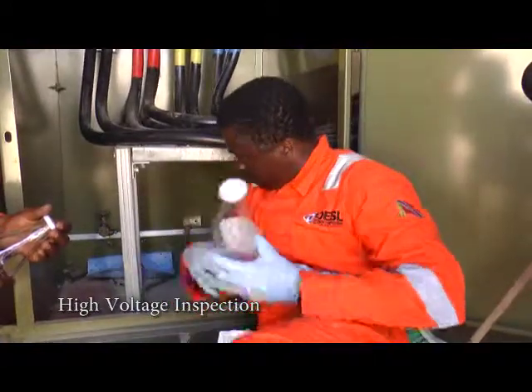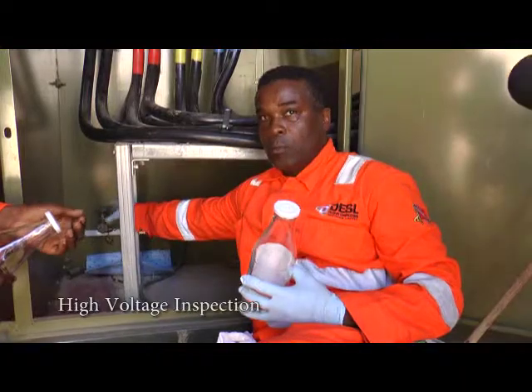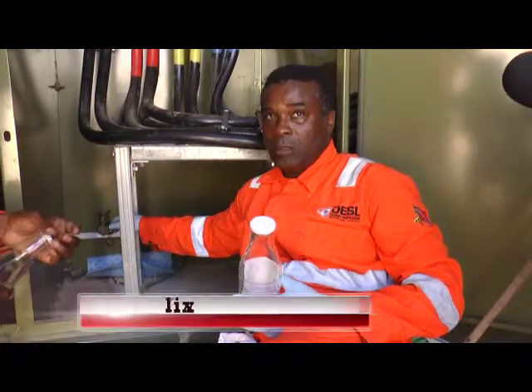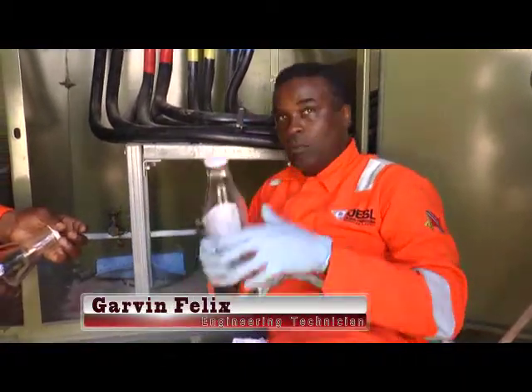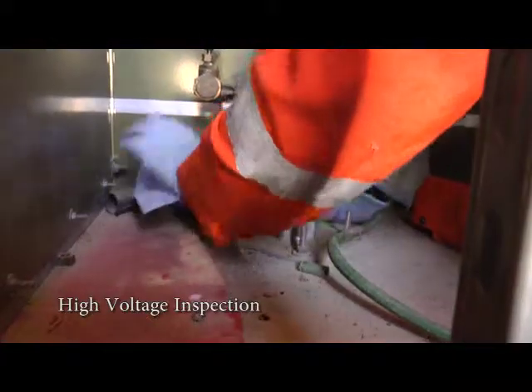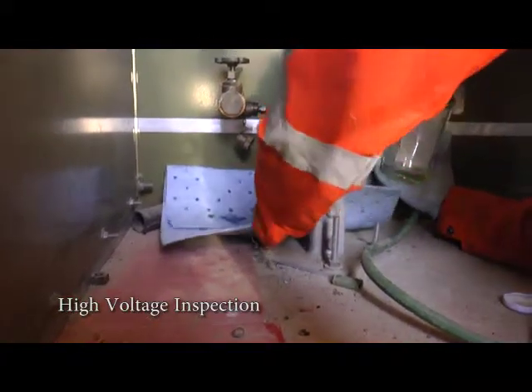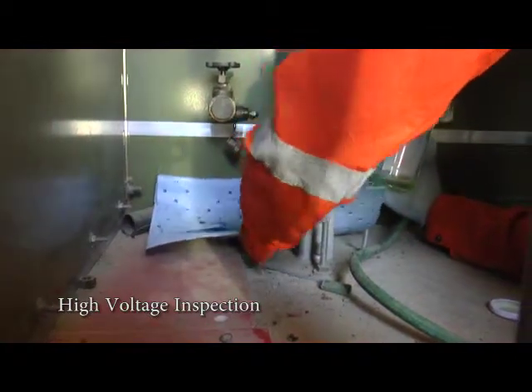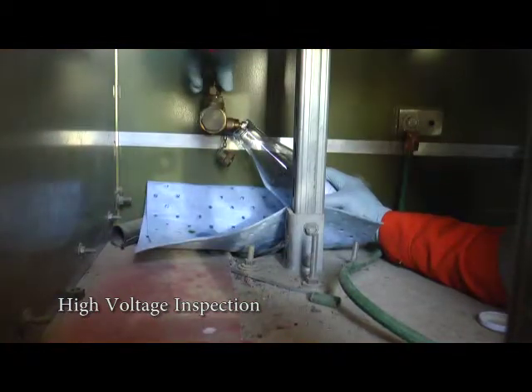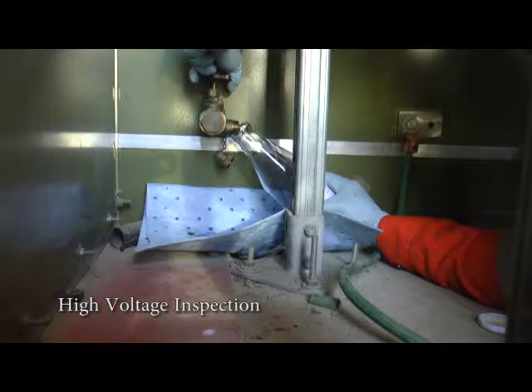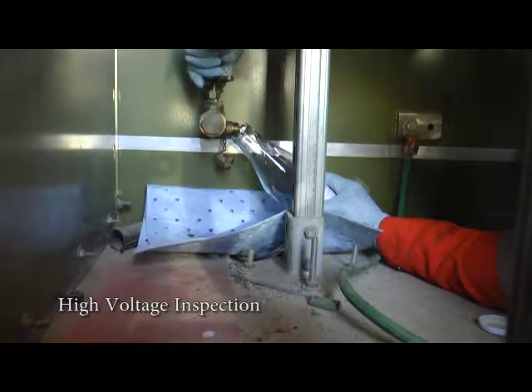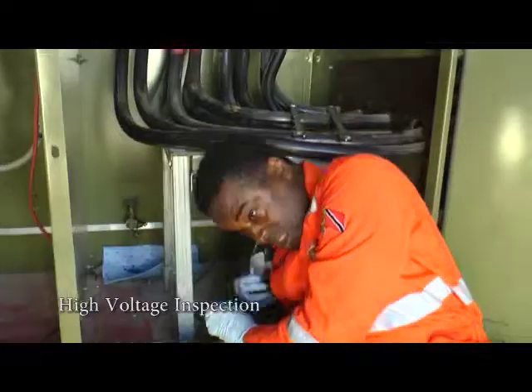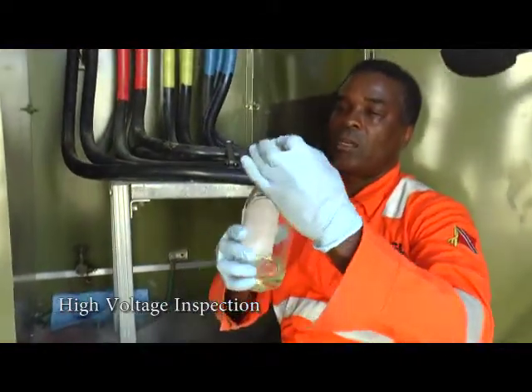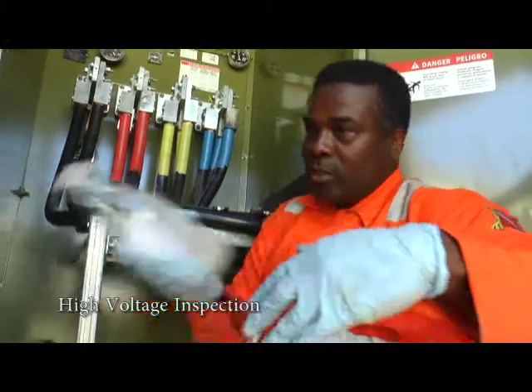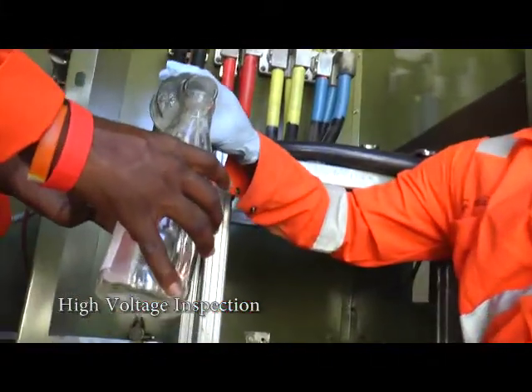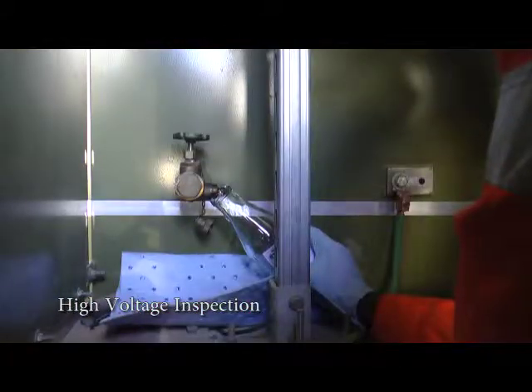Firstly, we clean around the pot where we're taking the oil sample, and then we take the oil sample. Put a spill mat on the ground because we don't want the oil to fall and spill on the ground. First, we take a little sample to rinse out the bottle. We rinse out the bottle twice. I take it, I close the cover, and I rinse it out. So I put it in this bottle here, and now I'm taking the sample.